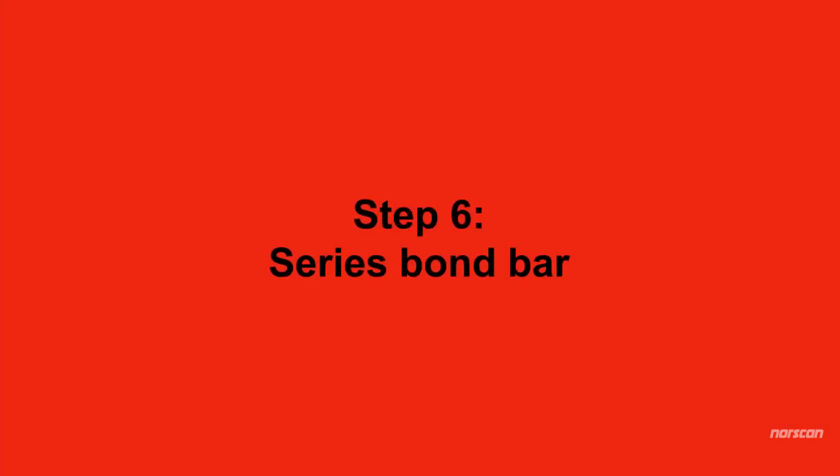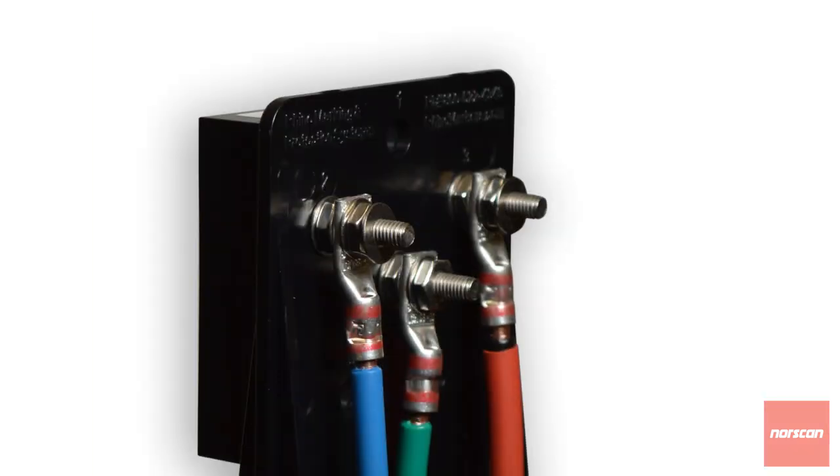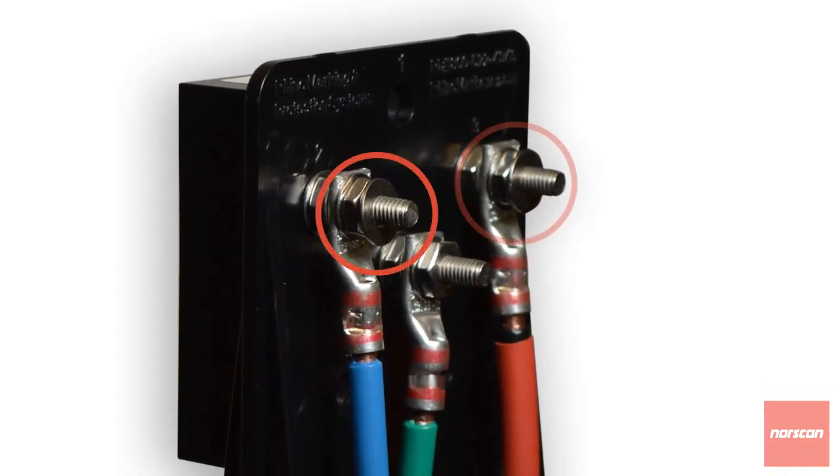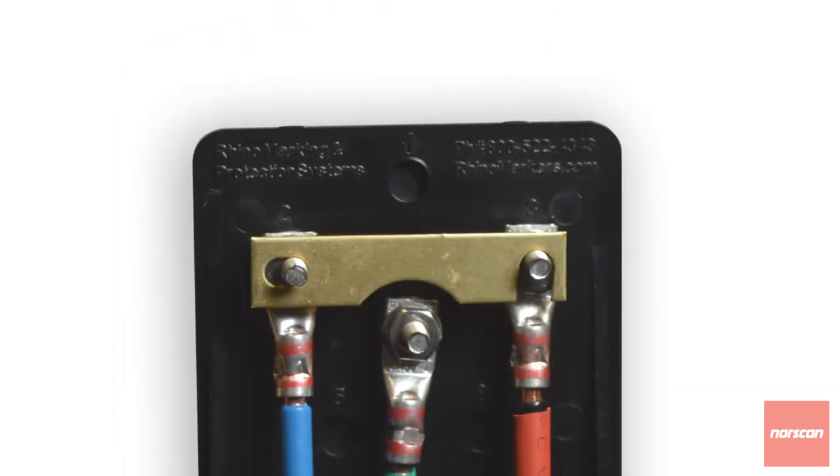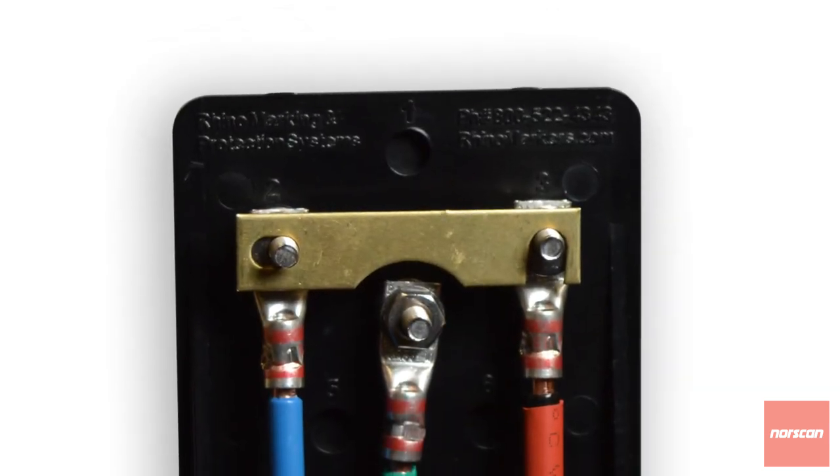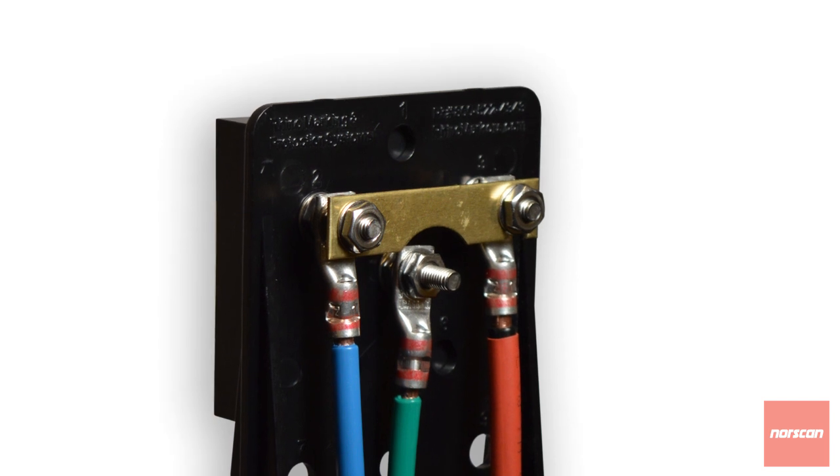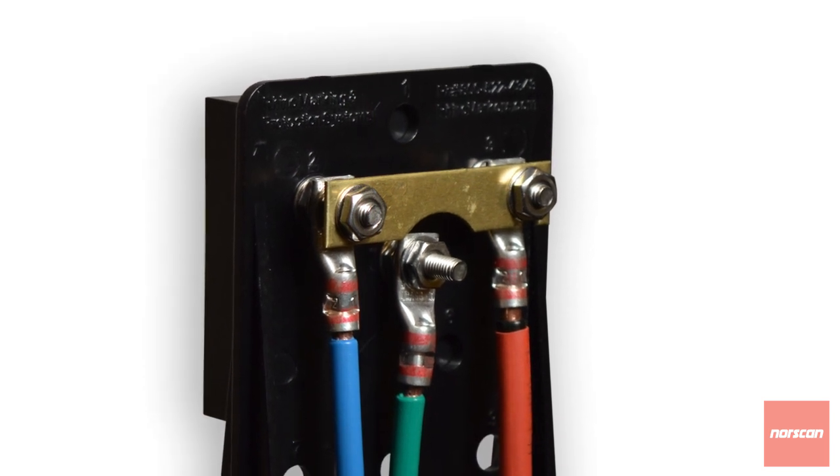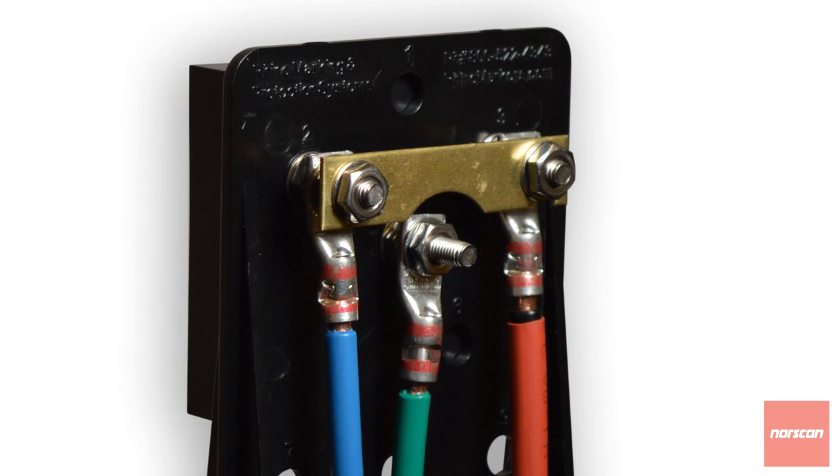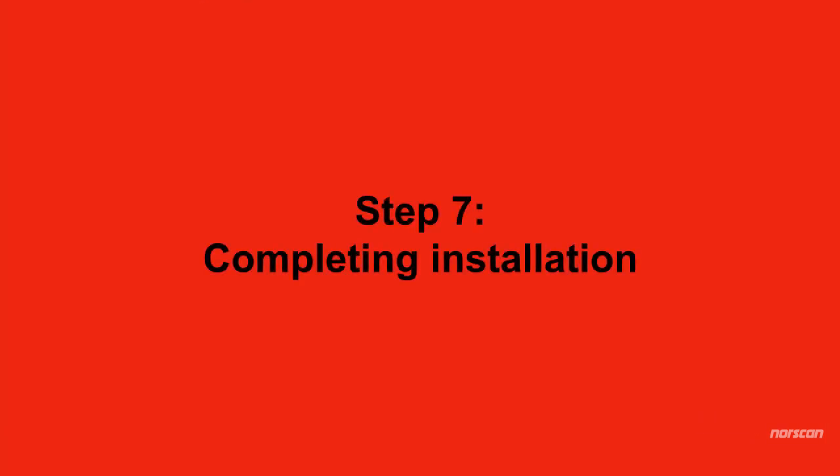Step 6: Series Bond Bar. Add one washer to each of the terminal posts numbers 2 and 3. Place the series bond bar onto those same terminals. Next, add the last washer and the final nut to each terminal. Secure the nuts tightly with a can wrench or nut driver.